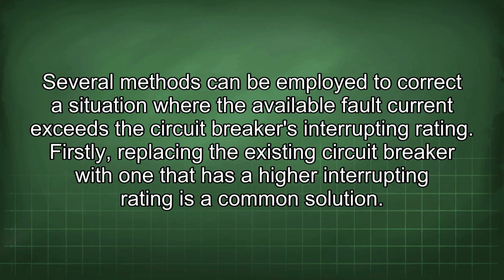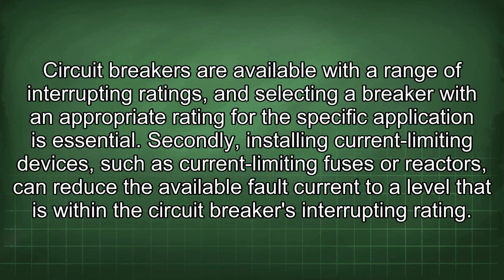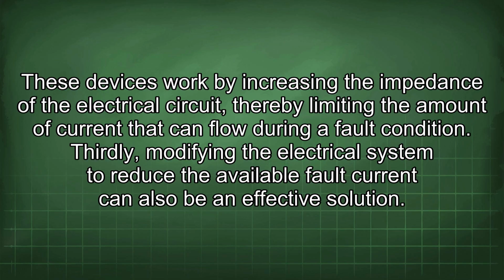Several methods can be employed to correct a situation where the available fault current exceeds the circuit breaker's interrupting rating. Firstly, replacing the existing circuit breaker with one that has a higher interrupting rating is a common solution. Circuit breakers are available with a range of interrupting ratings, and selecting a breaker with an appropriate rating for the specific application is essential. Secondly, installing current limiting devices, such as current limiting fuses or reactors, can reduce the available fault current to a level that is within the circuit breaker's interrupting rating. These devices work by increasing the impedance of the electrical circuit, thereby limiting the amount of current that can flow during a fault condition.